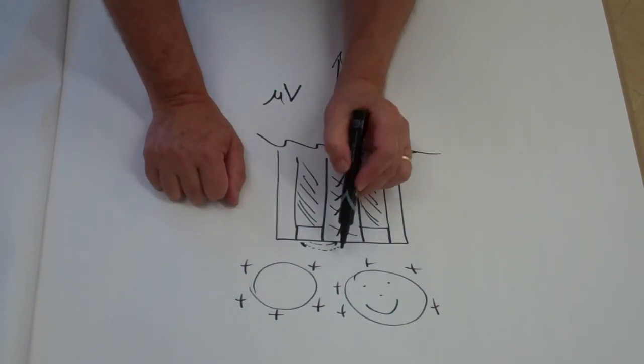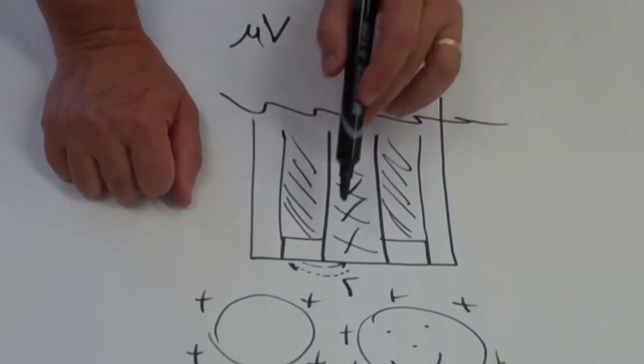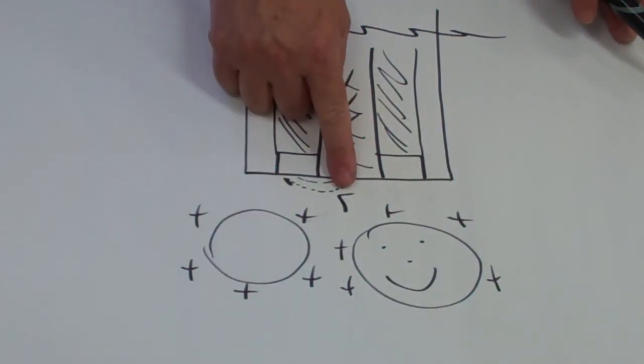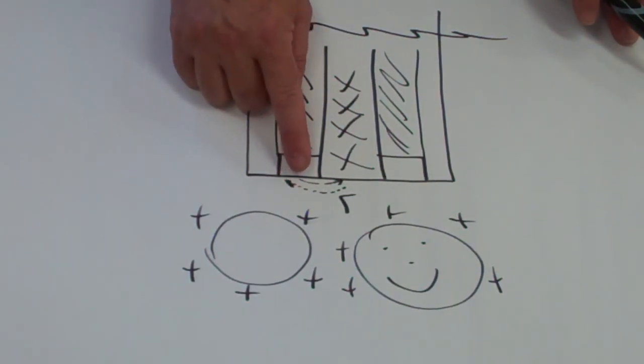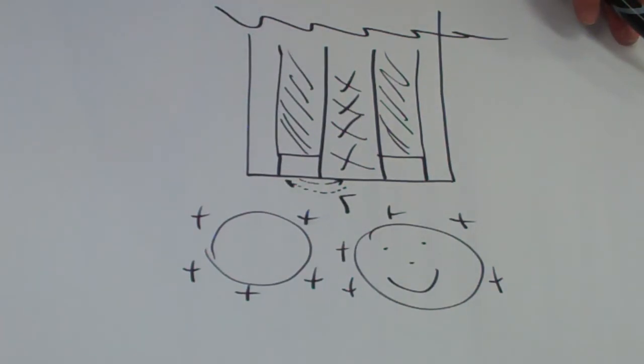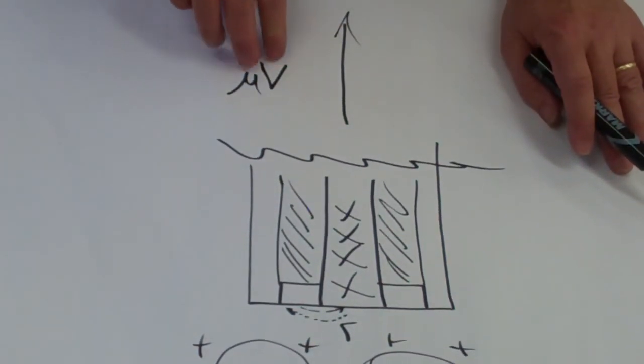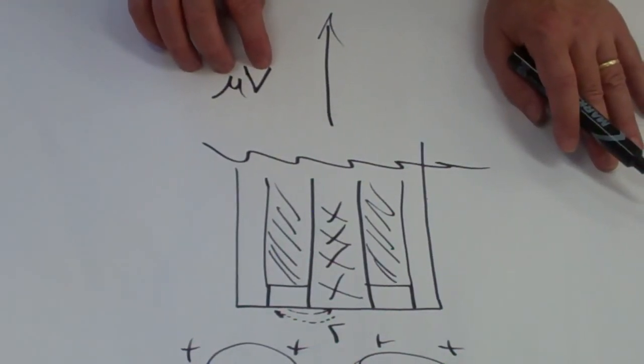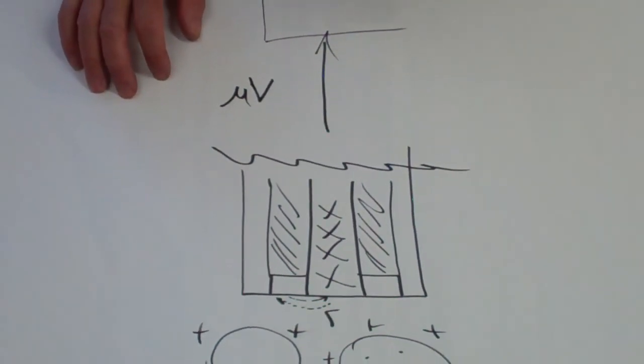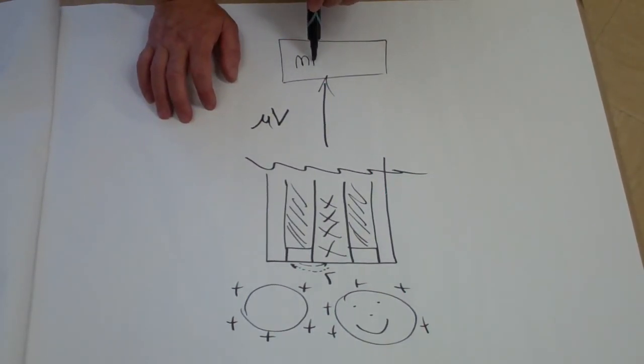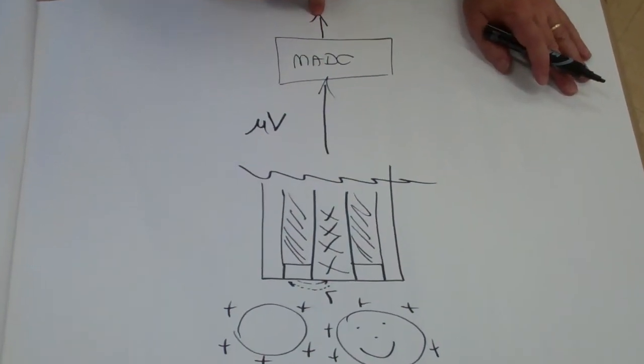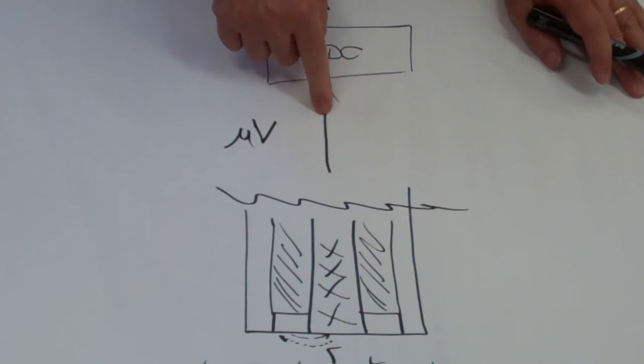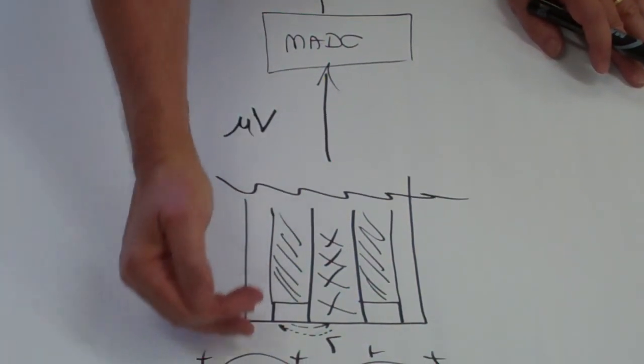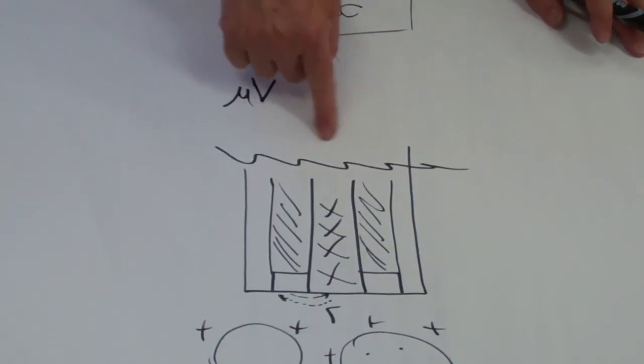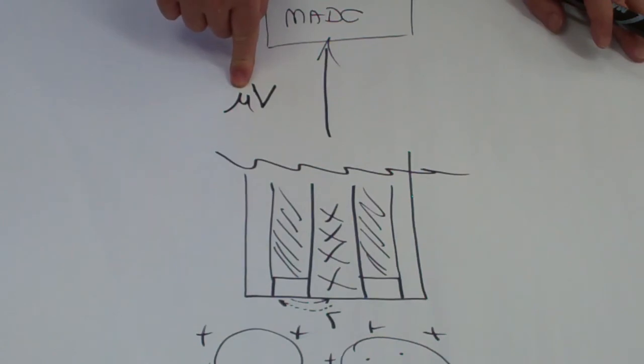When you have a pH of 7, there'll be no flow. As the pH goes up, you get flow in one direction. As it goes down, in a different direction. Therefore, this signal here can be a plus or minus, very low voltage and very high impedance signal. We convert this signal into typically milliamps, and that's what we transmit to the controller, because milliamp signals are strong, 4 to 20 typically. This signal is in a coaxial cable from the sensor, which is in contact with the ink, to the controller. This coax cable, if it's damaged, will mess up the signal and you're going to have problems.